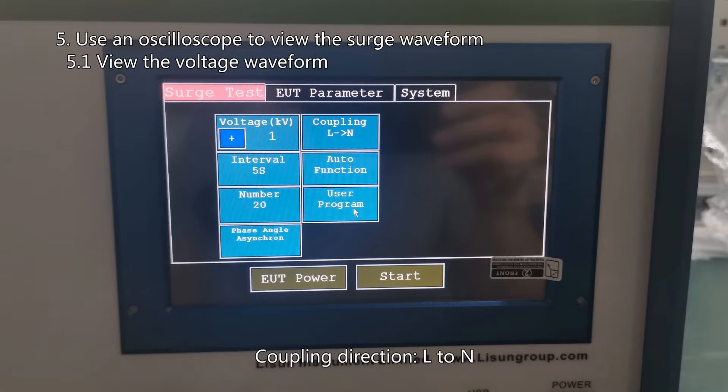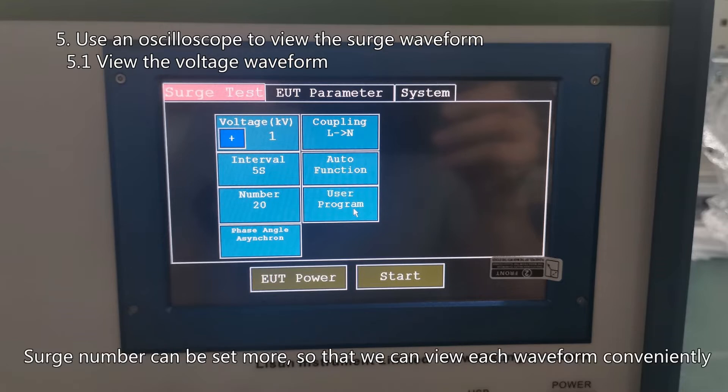Coupling direction, L to N. Interval, a short interval such as 5 seconds. Surge number can be set more, so that we can view each waveform conveniently.